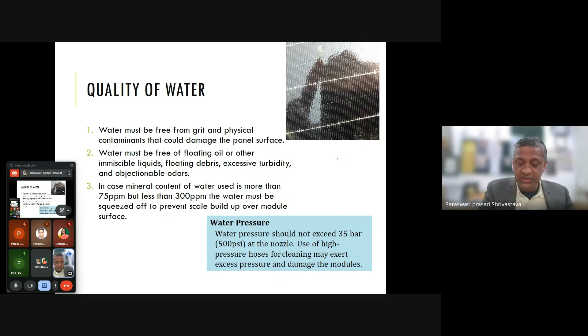After some months, you will find a whole layer of dirt on the lower part. Do not use abrasive or electric cleaners on the module. Particular attention should be taken to avoid the module back sheet or frame meeting sharp objects, as scratches may directly affect product safety. Do not use any degreaser on the module.